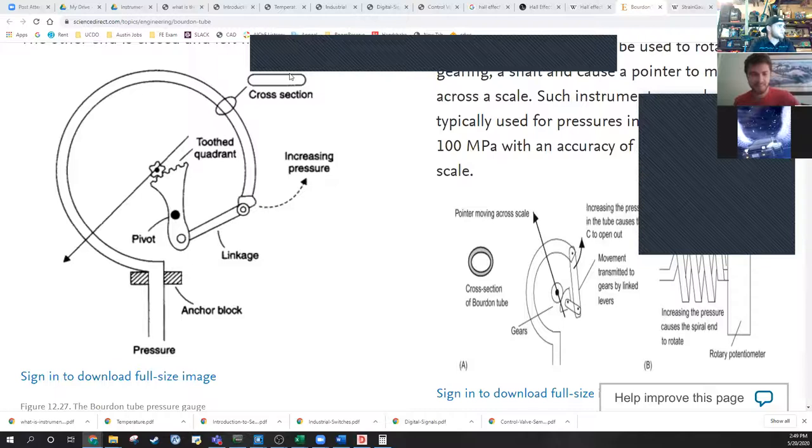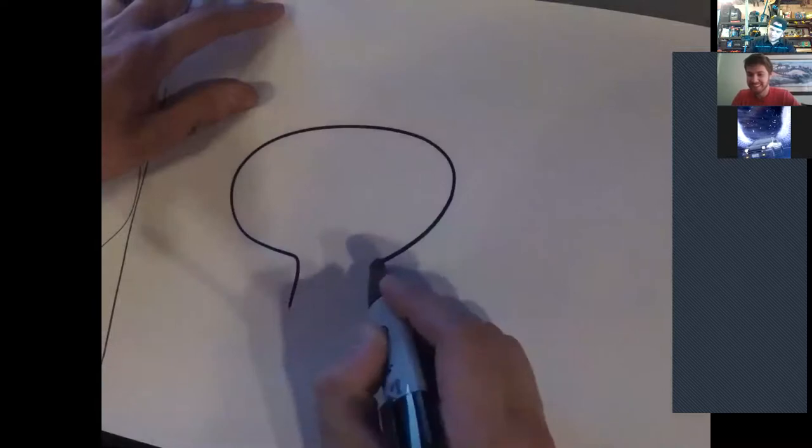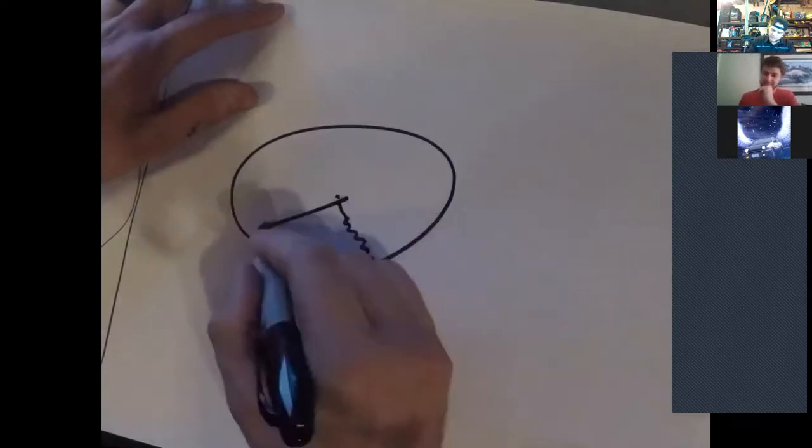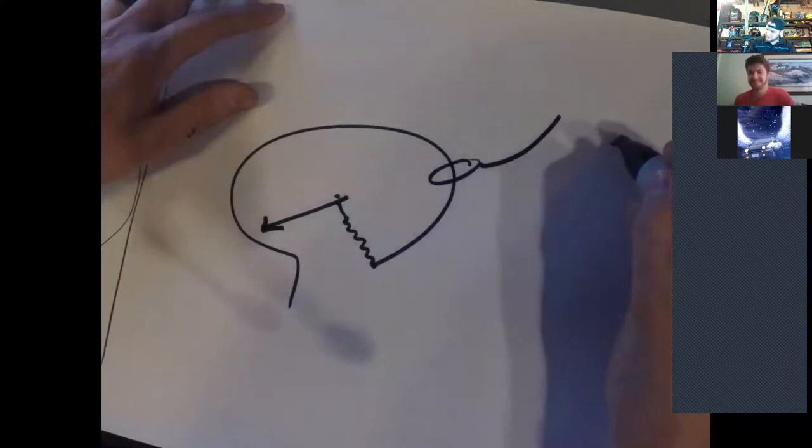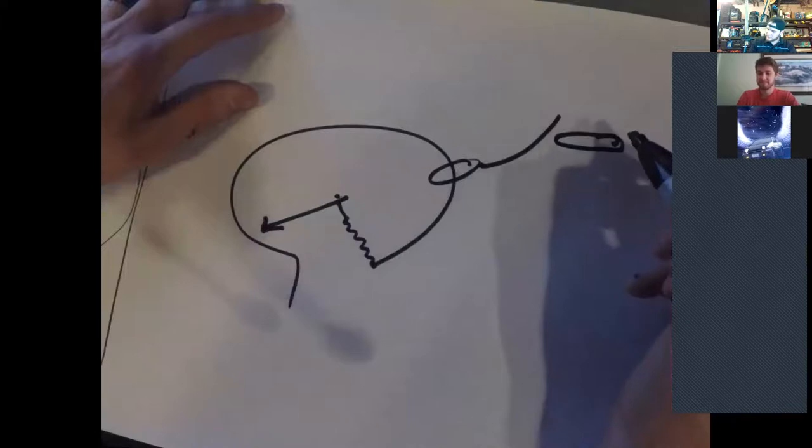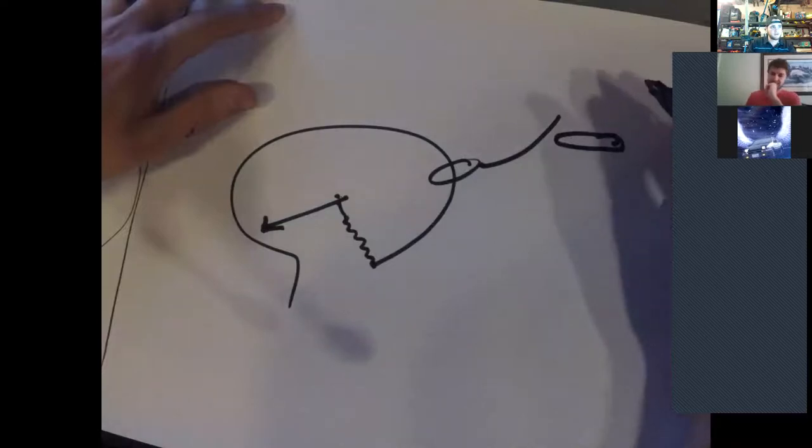So basically the way this works is you have a metal tube that has this gnarly cross-sectional geometry. And so as pressure increases in this tube, this tube wants to straighten out and pull basically pull up, which pulls on this linkage arm, which goes through the gears and pivots the needle.